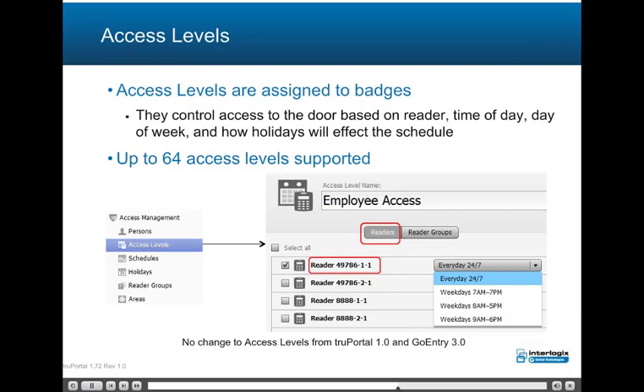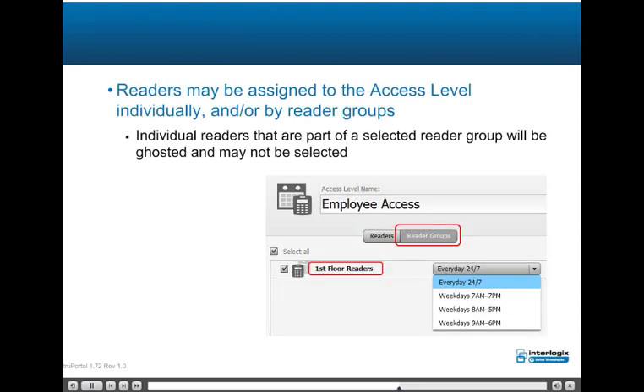Access levels are assigned to badges and control access to the door based on reader, time of day, day of week, and how holidays will affect the schedule. Up to 64 access levels are supported. Readers may be assigned to the access level individually and/or by reader groups. Individual readers that are part of a reader group selected in the access level will be ghosted and may not be selected.